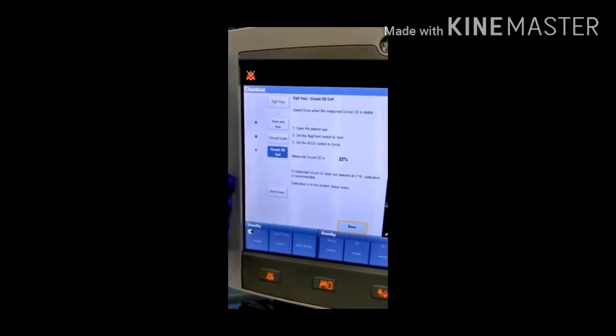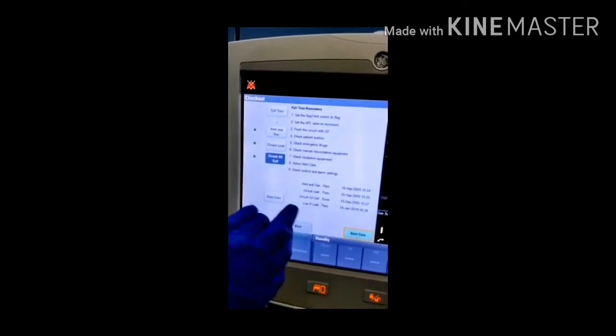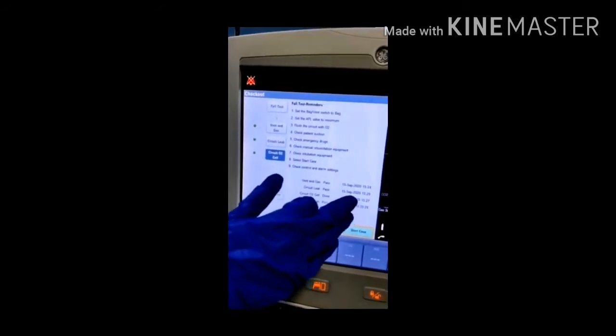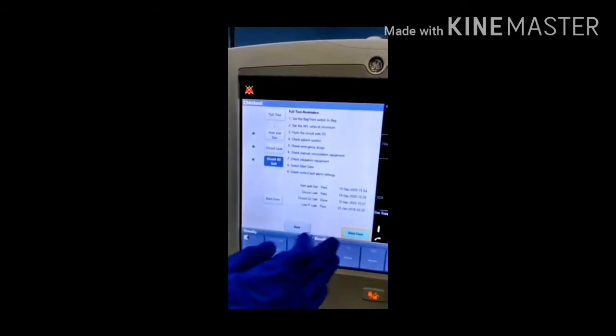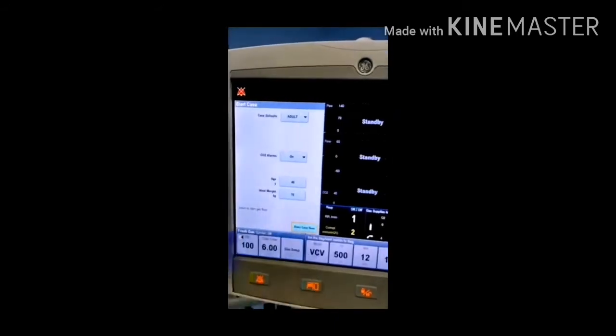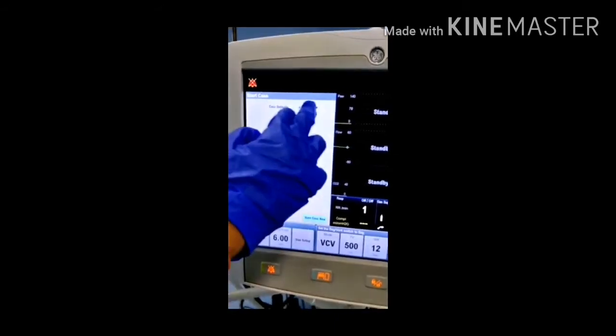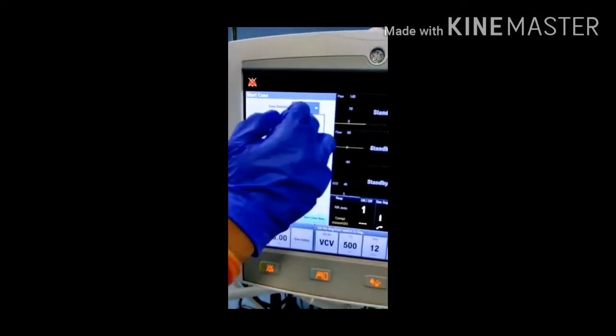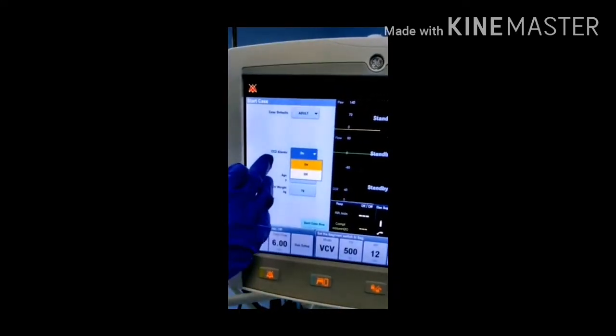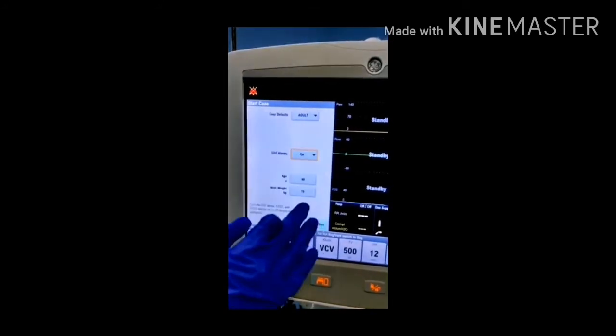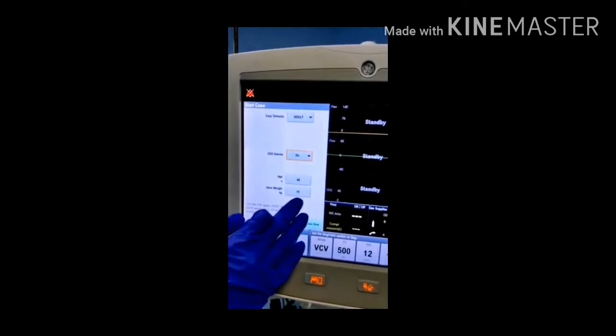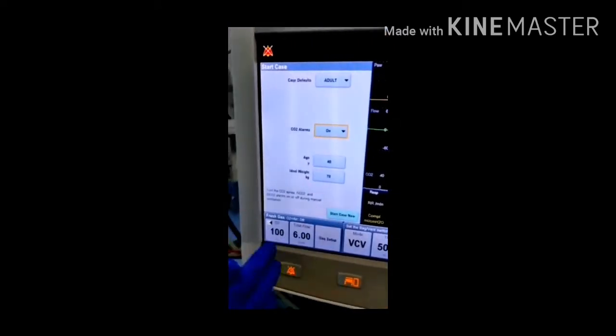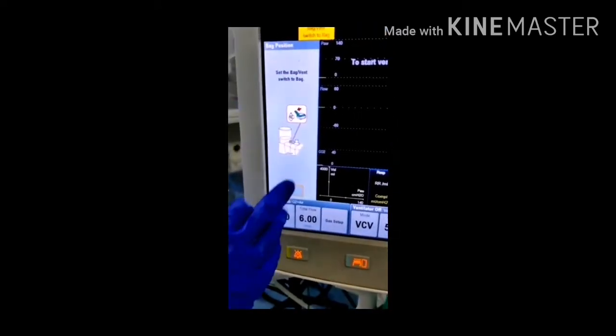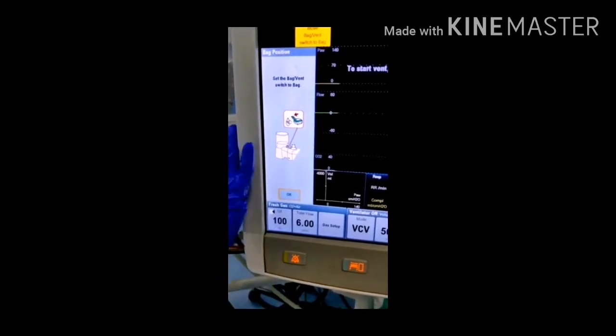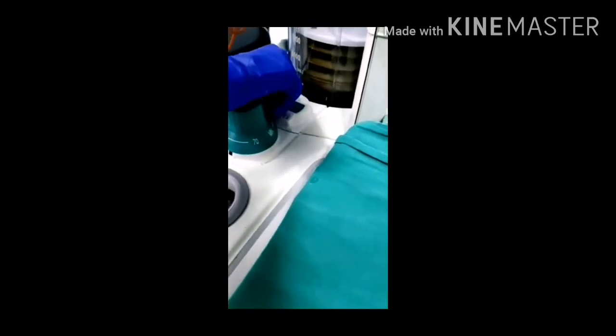Once it reaches this value, we will press done, and it would show that all the tests have been passed and the date and time at which it was performed. So you can now start the case. You can set the parameters from over here. We will select adult patient. CO2 alarms, whether you want them on or off. You can select the age of the patient, you can select the weight of the patient, and from here, to start the patient, you have to take the switches to bag mode and then vent.